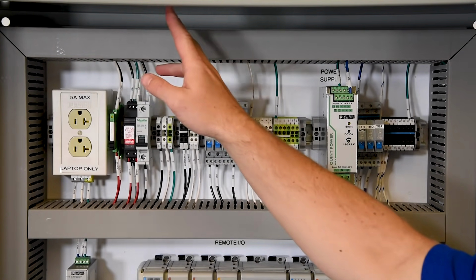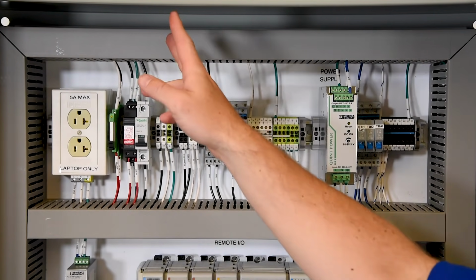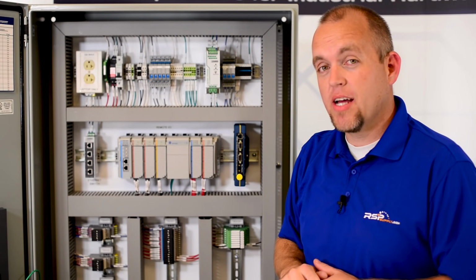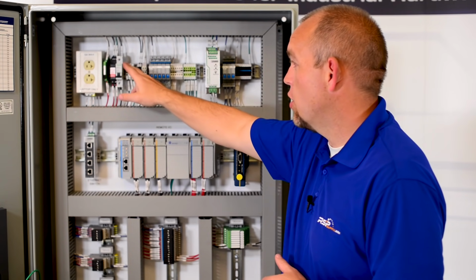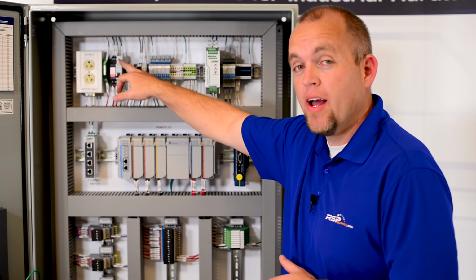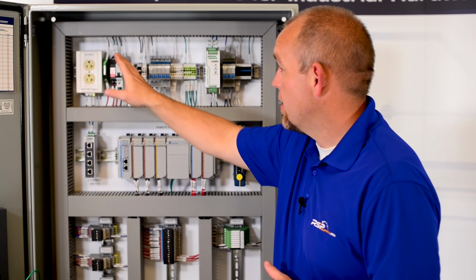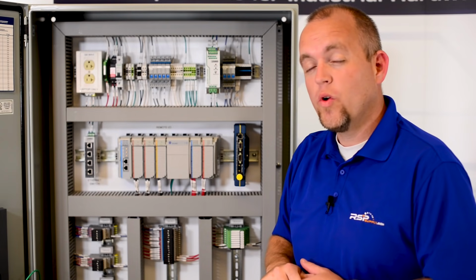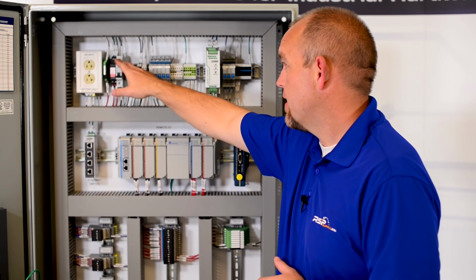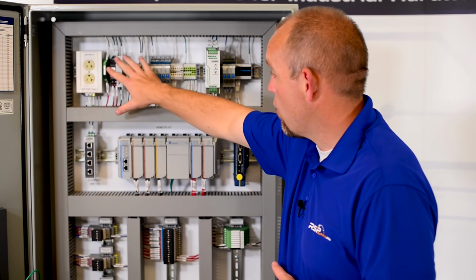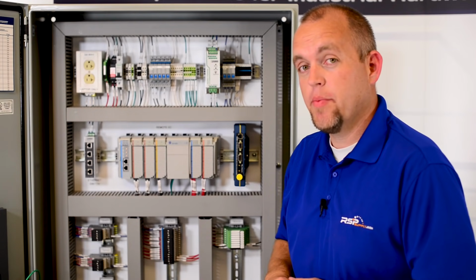We want to think about where power is going to be coming into our enclosure. Power typically comes in at the top of the enclosure, so we typically like to locate our main circuit breaker at the top of the enclosure, either on the left side or the right side. We typically see these mounted on the left side. This breaker will kill power to everything located within the panel.